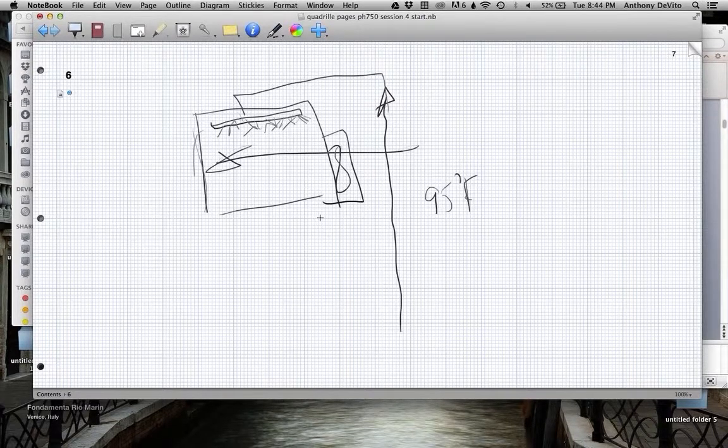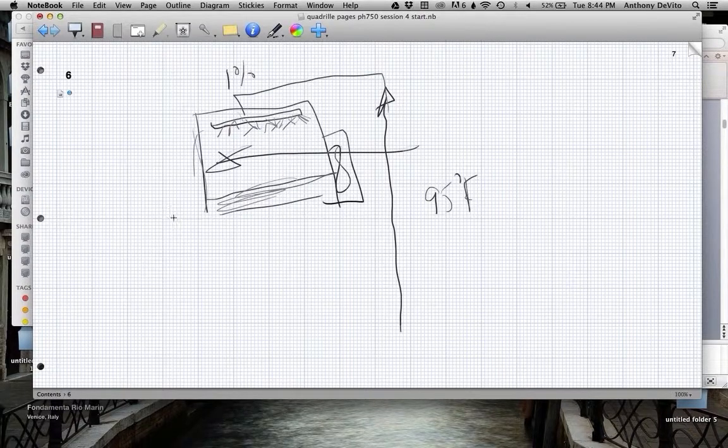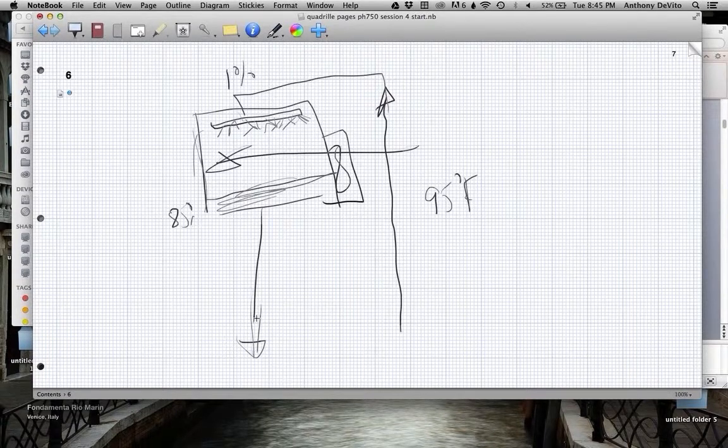It evaporates it and cools it. You get some sensible cooling, but your principal cooling is due to evaporation. Roughly 1% of that flow evaporates and then collects at the bottom in a sump. And that's enough to cool it 10 degrees. Now at 85 degrees, it goes back down, and you reuse it to recool that water.